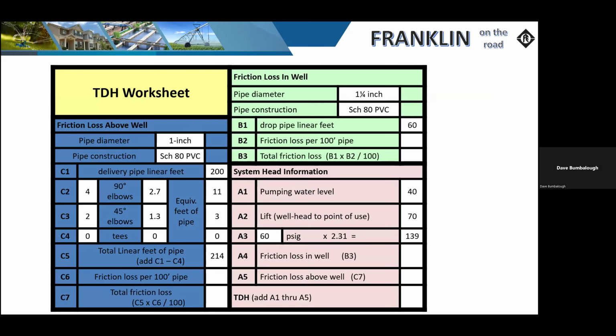So as we go back and plug those numbers in, it says those 4 90s are equivalent to about 11 foot of head loss. The 2 45s are equivalent to about 3. So we add all that up, and we're somewhere around 214 on the above-well losses.